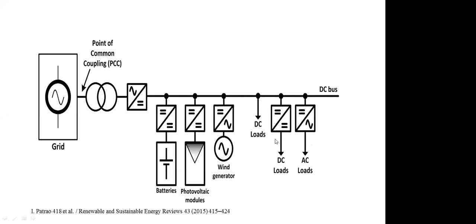Now, how can we go with the DC microgrid? Here you can see this as an extension of what I showed previously. I tried to work out these structures in my thesis also. So here you have PV, you can connect DC-DC; wind is AC to DC, and storage is DC to DC bus. If you want to supply AC loads, you have a DC to AC inverter and you supply the loads. If you have a DC load, you need a DC-DC converter, and even though you have a DC bus, it may be 380 volts or it may be 48 volts. So if you have a different voltage level, you need to go for a different converter rating or voltage level, because different devices may operate at different voltage levels. Chillers and similar loads operate at 380 volts or higher. LED lamps may operate at 12 or 24 volts. Some battery configurations may operate at 24 volts. Depending on the load, you need to configure your DC-DC converter accordingly.